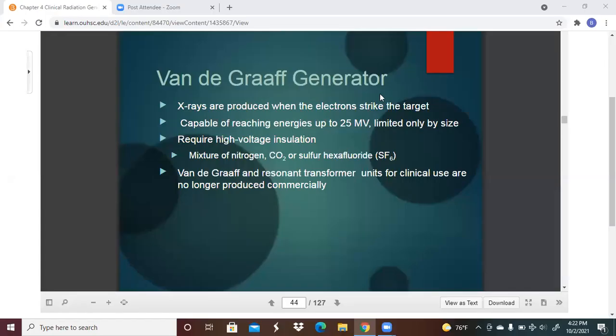All right, so here you've got your Van de Graaff generator. X-rays are produced when the electrons, of course, strike the target. They're capable of reaching energies up to 25 MV, and they're limited only by the size. It requires high voltage insulation, a mixture of nitrogen, CO2, and sulfur hexafluoride. Van de Graaff and resonant transformer units for clinical use are no longer produced commercially.